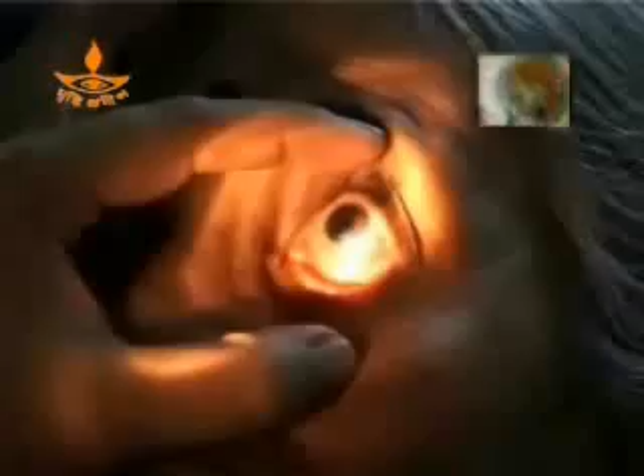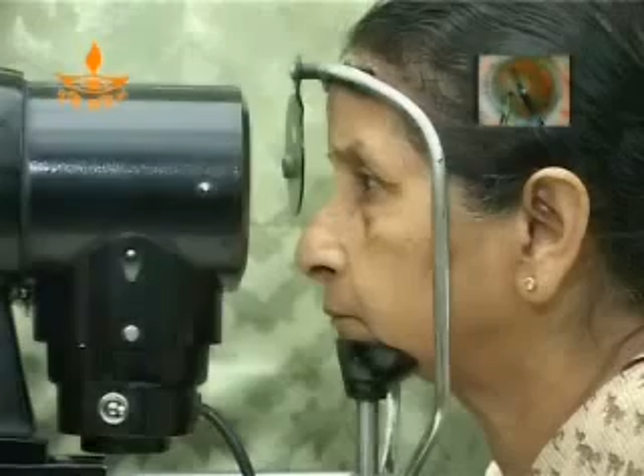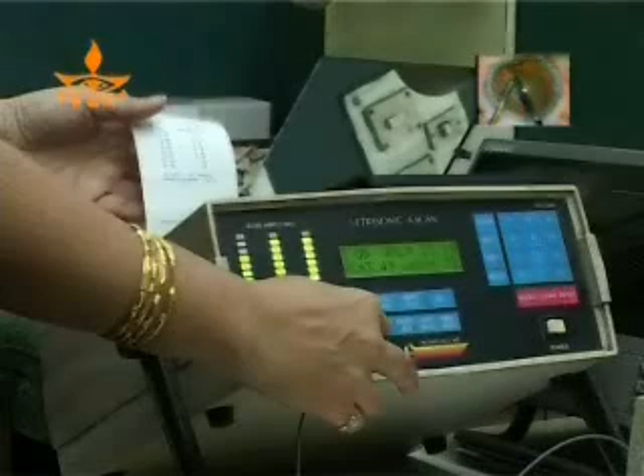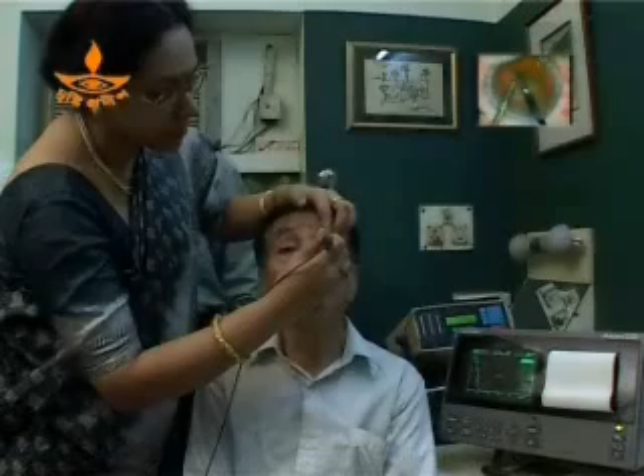Preoperative investigations. Apart from a thorough ophthalmological examination, certain preoperative laboratory tests and examinations are essential. One is the biometry test. Here the corneal curvature of the patient is measured by a keratometer, and then with an ultrasound A-scan machine, the anteroposterior length of the eye is calculated. From the above two measurements, a computer-generated printout from the biometry machine gives the intraocular lens power of the artificial lens to be implanted during cataract surgery. We have two very sophisticated machines for accurate biometry testing.